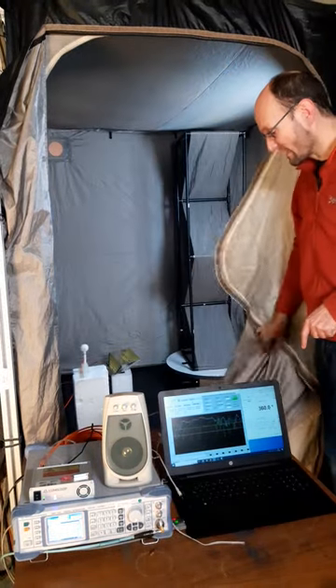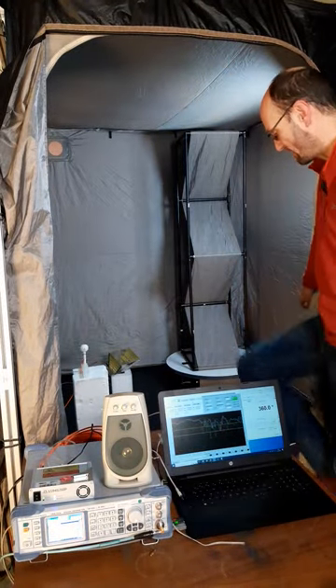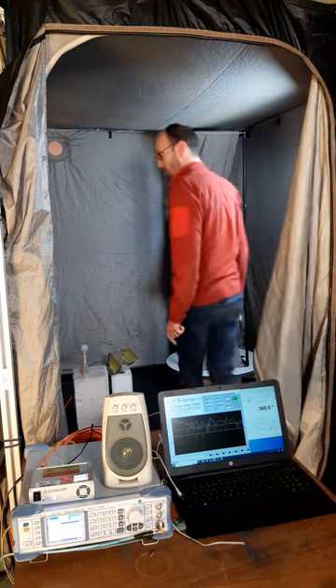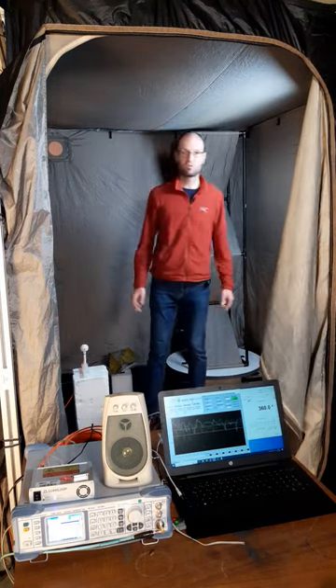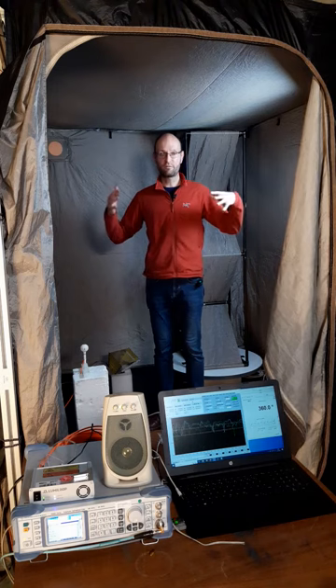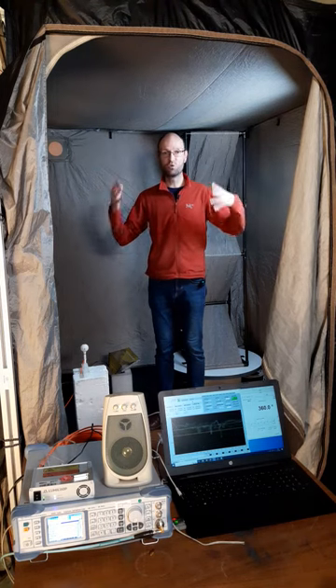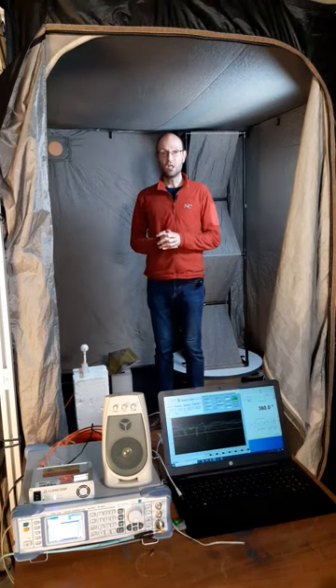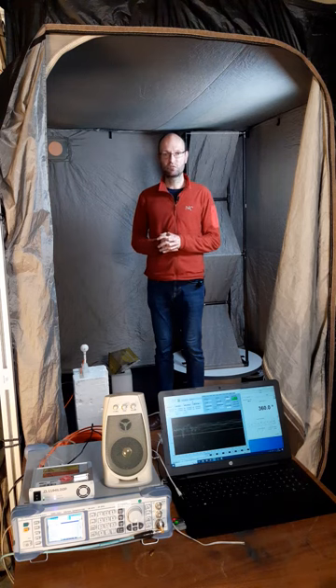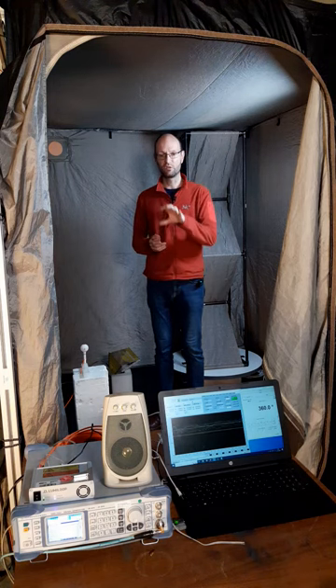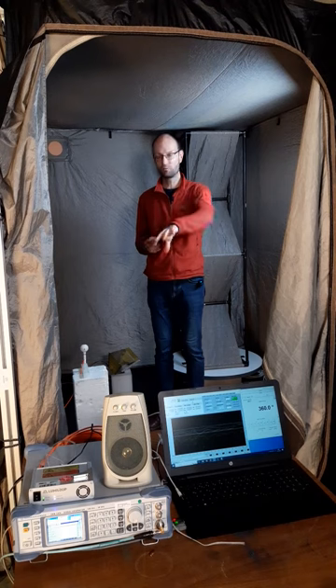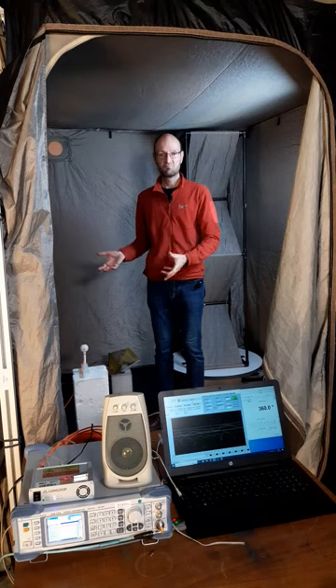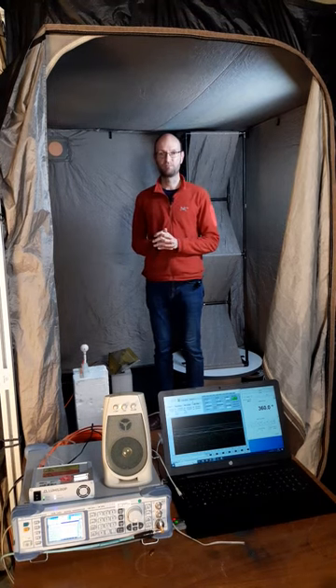So this is definitely one big advantage of such mode steered or reverberation chambers. Due to the high quality factor of the field and the high Q of the resonator, you get rather high field strengths with small input powers only. So with this 100 milliwatt input power here, we get a couple of volts per meter.